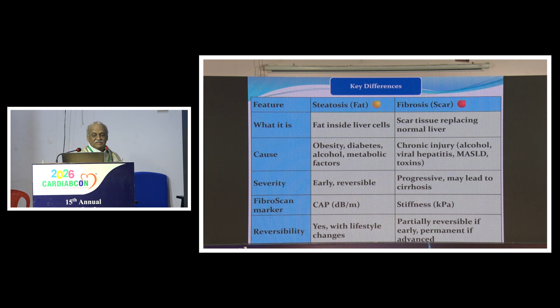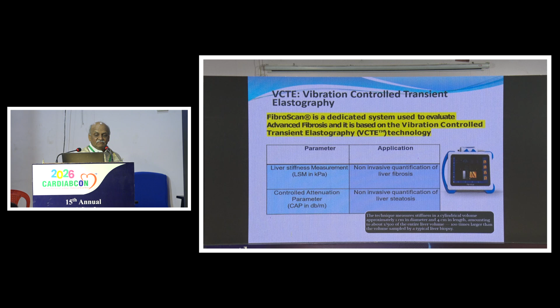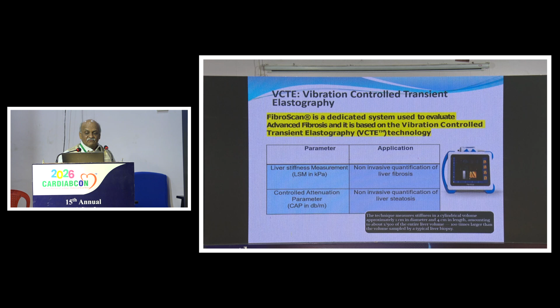So this is the vibration controlled transient elastography. This is the principle of ultrasonography that is used in FibroScan. It is a dedicated system used to evaluate advanced fibrosis, and it is based on the vibration controlled transient elastography technology. Liver stiffness measurement, in kPa, is non-invasive quantification of liver fibrosis, while controlled attenuation parameter, in decibel per meter, is non-invasive quantification of liver steatosis. The technique measures stiffness in a cylindrical volume approximately 1 centimeter in diameter and 4 centimeter in length, amounting to about 1 by 500 of the entire liver volume, 100 times larger than the volume sampled by a typical liver biopsy.